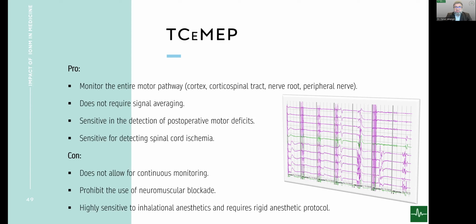On the con side, MEP cannot be done continuously because every time you do it, the patient jumps or moves, depending on the patient, the team, and the placement of the electrode. Sometimes the patient doesn't jump that much. Sometimes you have to change the parameters. You can do that, but it's still not continuous. It's every 1 minute, or twice a minute, or 3 minutes, every 5, 6 minutes. But it should not be done more than 4 or 5 minutes apart, because if there are ischemic changes and you're doing motor evoked potentials every 15 or 20 minutes, the patient is already compromised during that time.